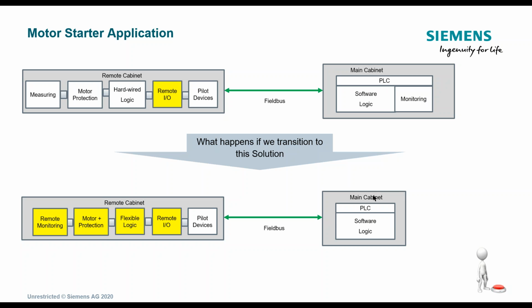So what we're doing is you're seeing that the controller is now becoming more of a traffic cop, if I could be so bold to say, trafficking and monitoring alarms coming from the field in the remote I/O cabinets. This unit is taking care of the remote monitoring and the motor protection. It has flexible logic in it to take care of scenarios that may arise in the field. And then it has remote I/O, and then it has the pilot devices.